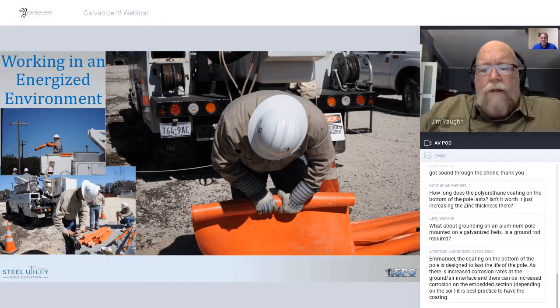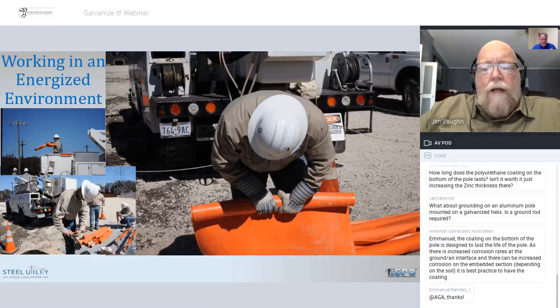And I agree with that statement for the poles that we've investigated after we've had them in the ground for a while. About aluminum poles mounted on a galvanized helix: the galvanic series reaction between galvanized and aluminum is very, very, very low. And actually you improve the life of the galvanized and aluminum by bonding the aluminum to the steel.